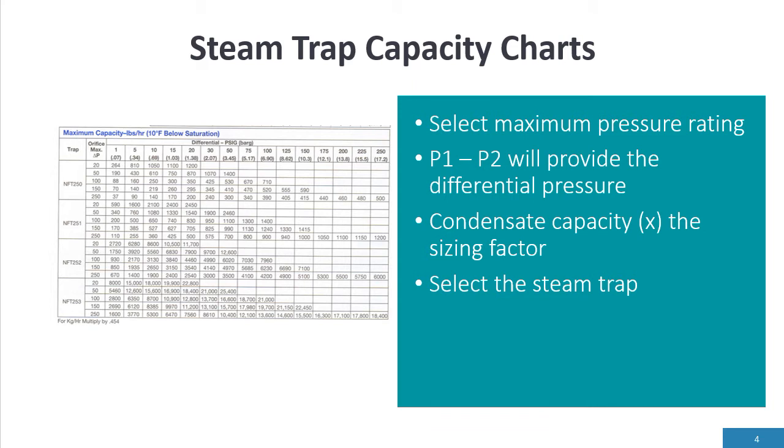Therefore we select a maximum pressure rating. The maximum pressure rating would be 150 psi, 366 degrees. Then we come up with P1 minus P2, which on our example we came up with a differential pressure of 55 psi. The condensate capacity sizing factor will take 200 pounds per hour with a sizing factor to 600 pounds per hour.